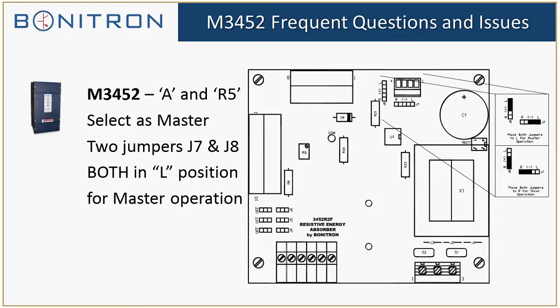The customer can then modify these to either be master or slave by setting these jumpers J7 and J8 on this board to the position L for master operation. If they want slave operation, it should be both in the R position. So the next slide is actually a picture of this, a picture of the actual board.